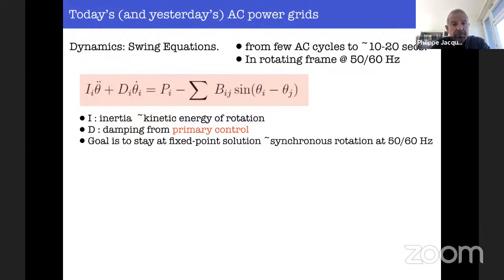The second derivative of the voltage angle comes about because you took the derivative with respect to time of the kinetic energy of rotation of your rotating machine. So I is, in some units, inertia. The first order term is damping, but you need to understand these equations are written in a rotating frame at 50 Hertz in Europe, 60 Hertz in North America. That means this damping doesn't damp you down to no motion at 0 Hertz, but damps you to 50 or 60 Hertz. So that's not physical damping, it's not friction, it's actually control, and it's built into some of these machines that we have.